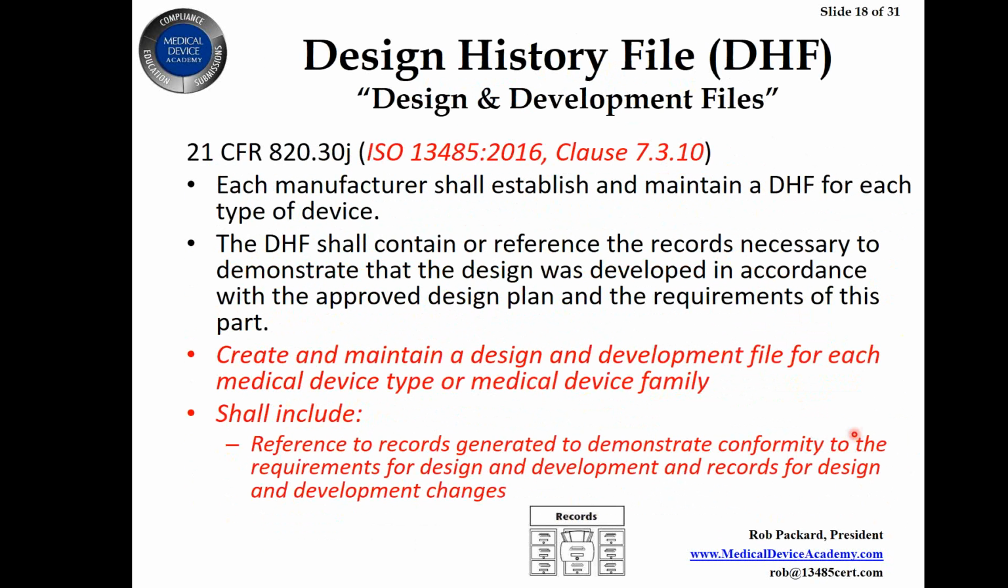And this brings us to our final requirement, which is the design history file requirement, which is clause 21 CFR 820.30(j) and ISO 13485:2016 clause 7.3.10. The phrase used in the ISO standard is design and development files.